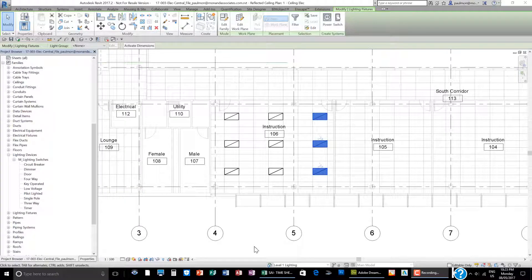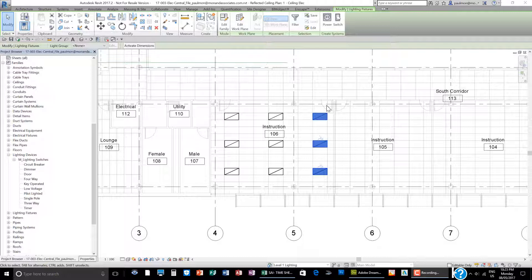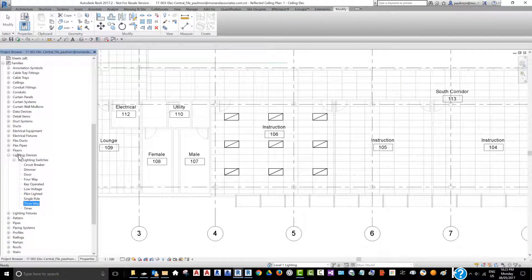Now we're going to look at creating a 3-way switch in Revit 2017. I already placed a number of light fixtures in this room. Because this room has two doors, it would be very likely that we could use a 3-way switch system by the doors. I'm going to click on the 3-way switch from the library. From the project browser under family, lighting device, we have M lighting switch.